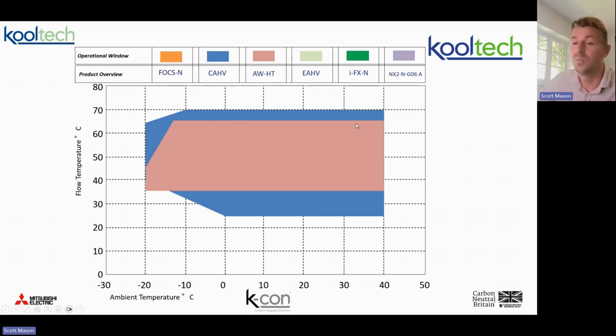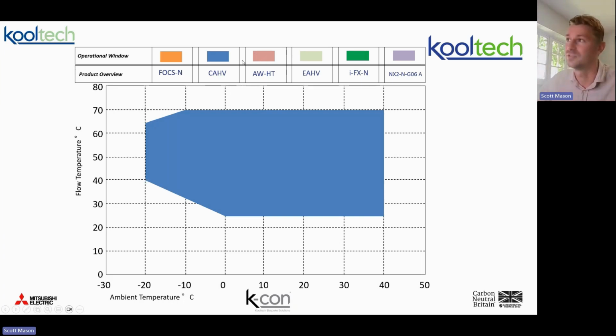However, from a global warming potential point of view, the refrigerant's probably not the best, because the sizes I can match on a modular basis with the CAHVR. So the right thing to do is lead with the CAHVR, because the CAHVR has a refrigerant global warming potential of 148 and the AWHT sits closer to 2000. So it's a totally different thing when it comes to environmental impact from the refrigerant choice.